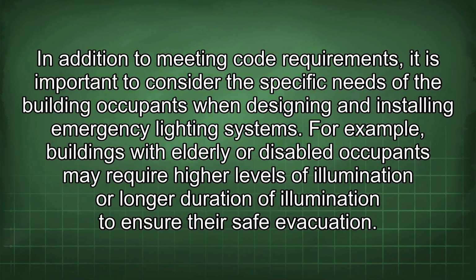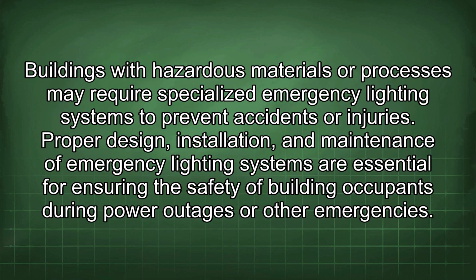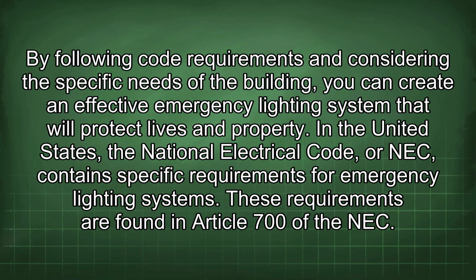For example, buildings with elderly or disabled occupants may require higher levels of illumination or longer duration of illumination to ensure their safe evacuation. Buildings with hazardous materials or processes may require specialized emergency lighting systems to prevent accidents or injuries. Proper design, installation, and maintenance of emergency lighting systems are essential for ensuring the safety of building occupants during power outages or other emergencies. By following code requirements and considering the specific needs of the building, you can create an effective emergency lighting system that will protect lives and property.